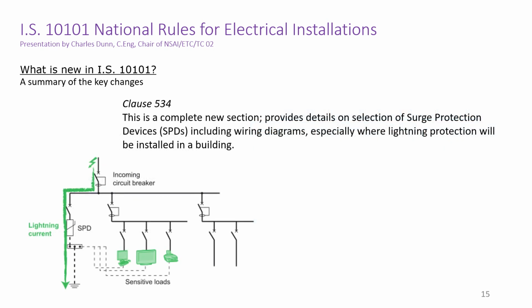Surge protection is dealt with in clause 534, which is a completely new section. It provides details on selection of surge protection devices, SPDs, including wiring diagrams, especially where lightning protection will be installed in a building. Surge protection was previously considered for protecting against lightning surges. Ireland is not very prone to lightning strikes, so we have not usually paid much attention to surge protection.